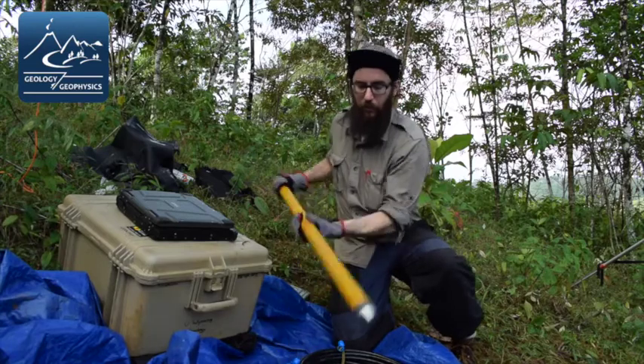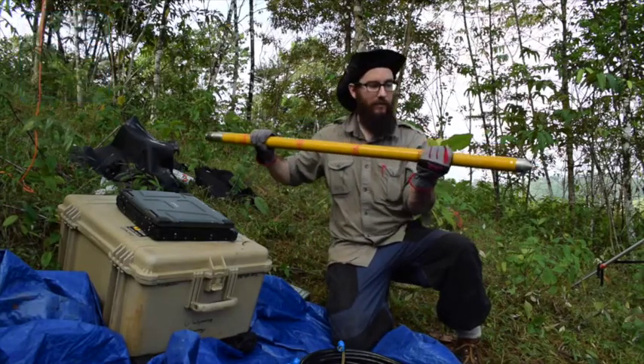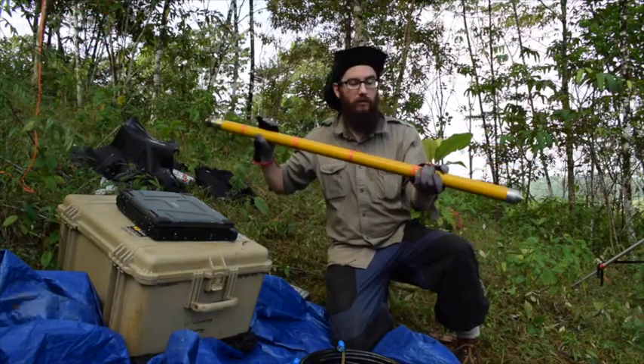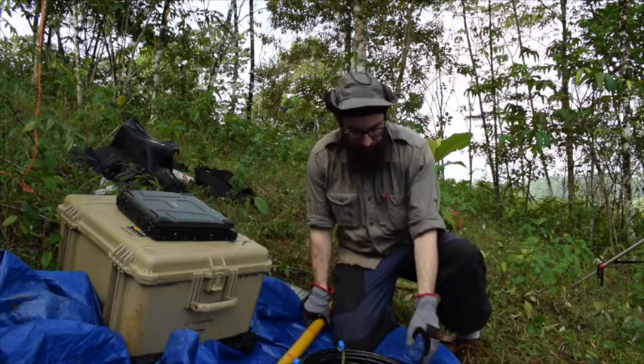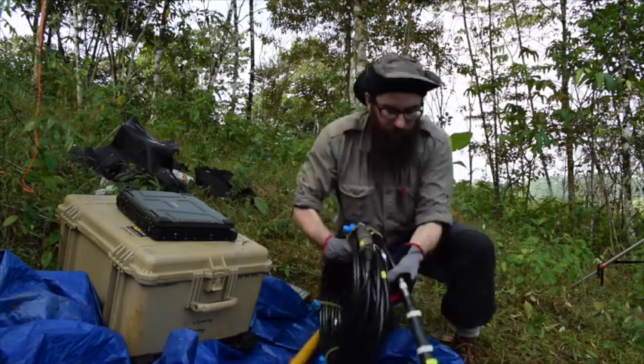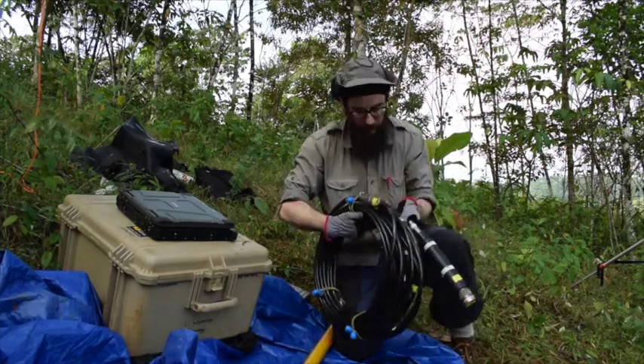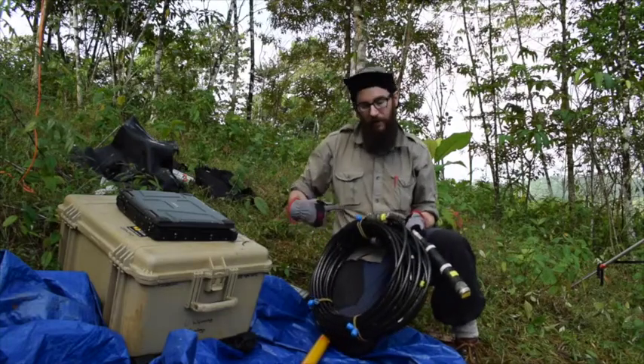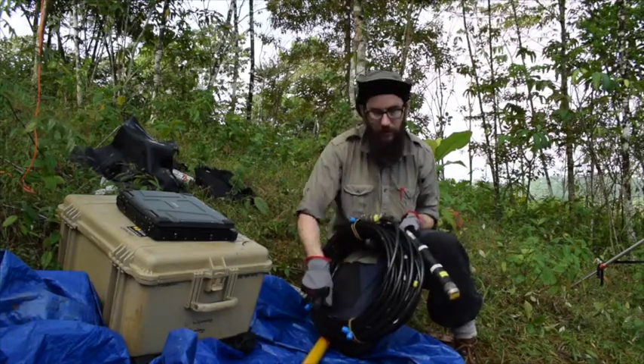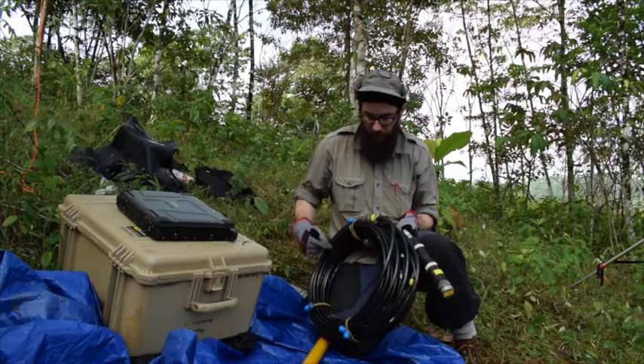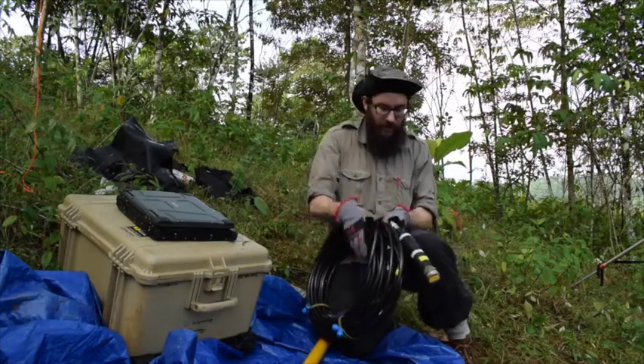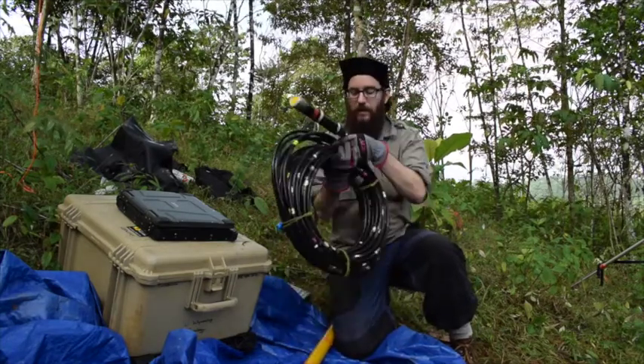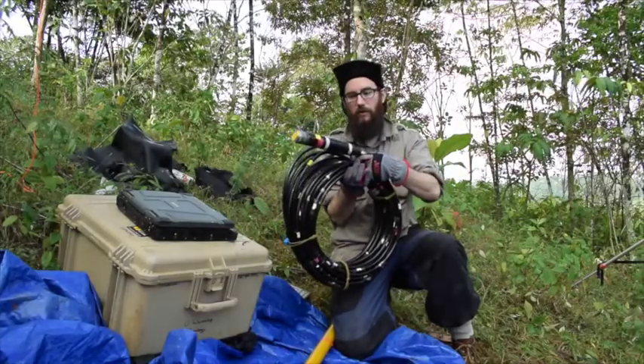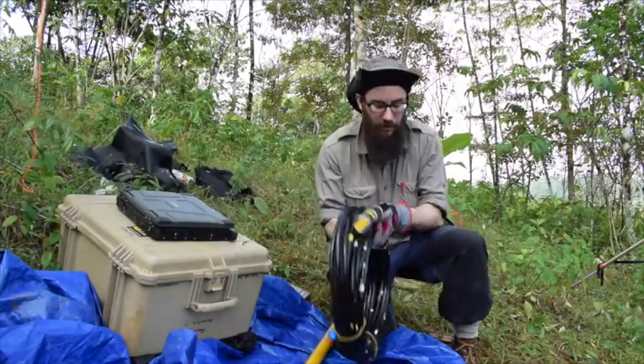There's a probe, so this has strong magnets in it, so keep it away from your wallet, your cell phone, and pacemakers. There's the cable. And it says minimum bend radius of 12 inches, so never roll it any tighter than a 12-inch circle. And then you have to be really careful of the cable head here, that this also doesn't bend too far. It's kind of heavy, so it's easy for that to happen accidentally.